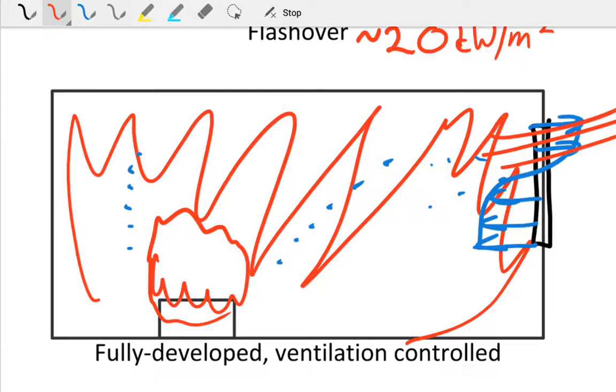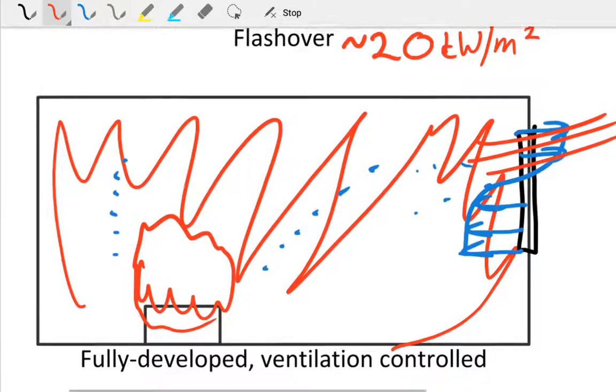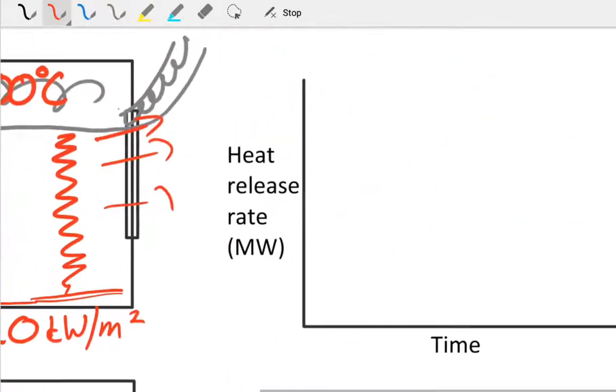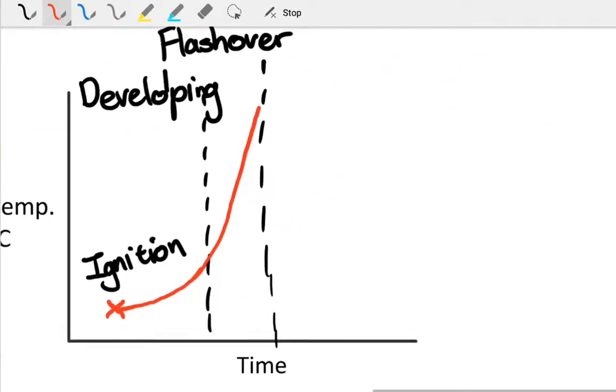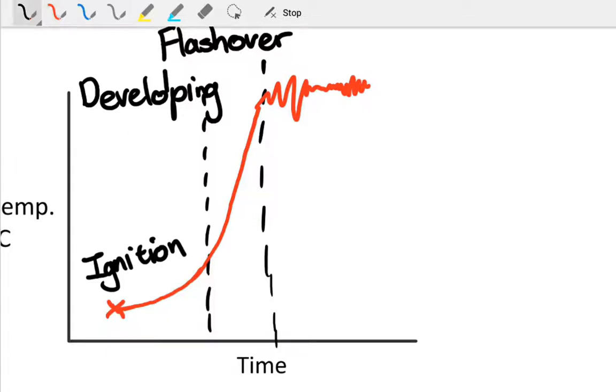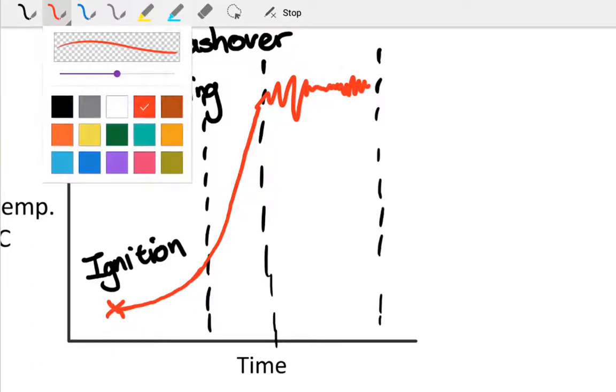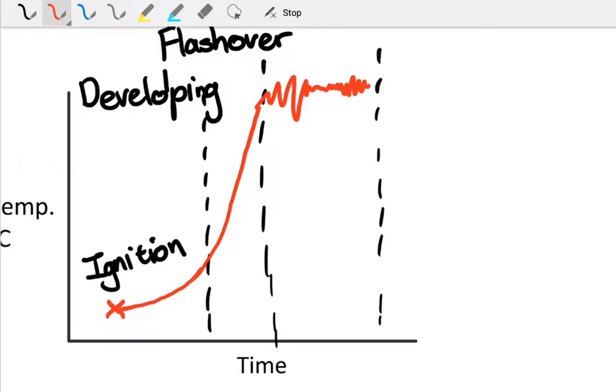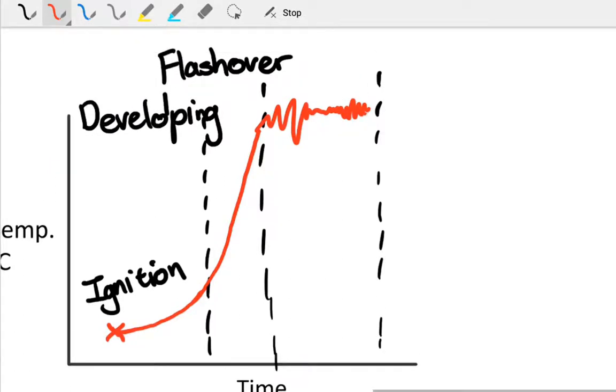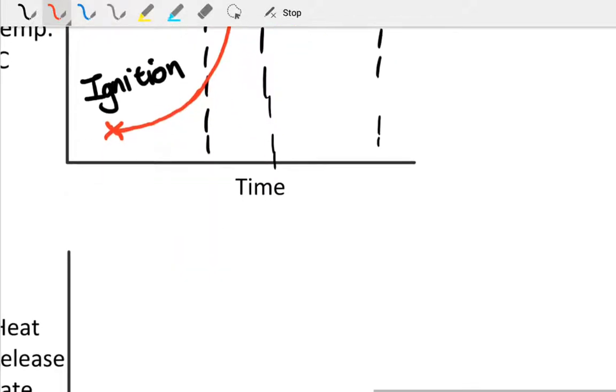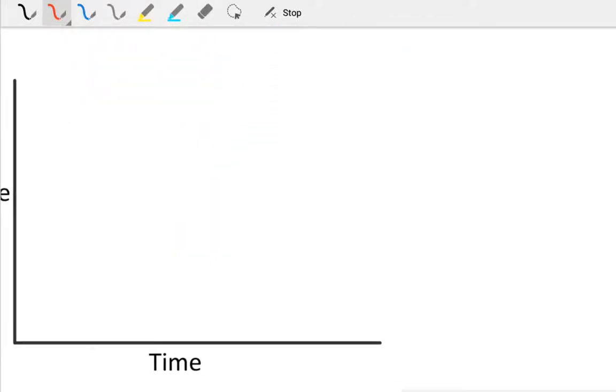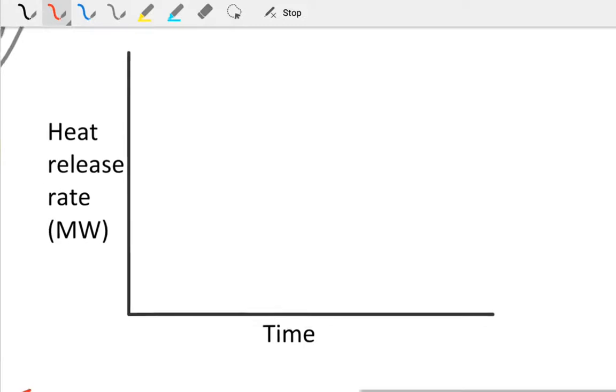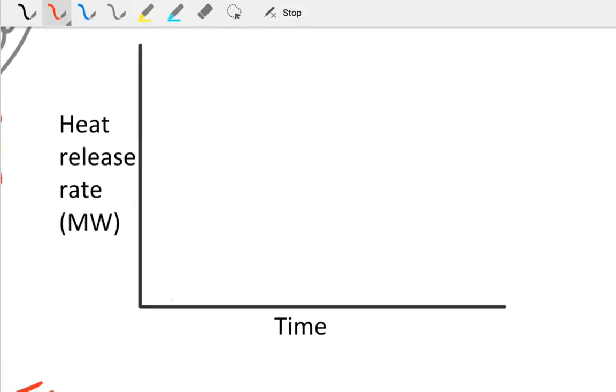Once again, this is the fully developed phase, and the burning rate is controlled by the amount of oxygen—it's ventilation controlled. It sort of flat lines, and there's always fluctuations in your temperature measurements, but we'll have approximately constant temperature in the room as it can't burn any faster. It might get a little bit up, a little bit down depending on what's going on. This is associated with a maximum heat release rate. If we simply use a t-squared fire, if this is now our heat release rate, it will start at ignition, and then as it ignites a wastebasket or something like that, you might have 100 or 200 or 300 kilowatts.